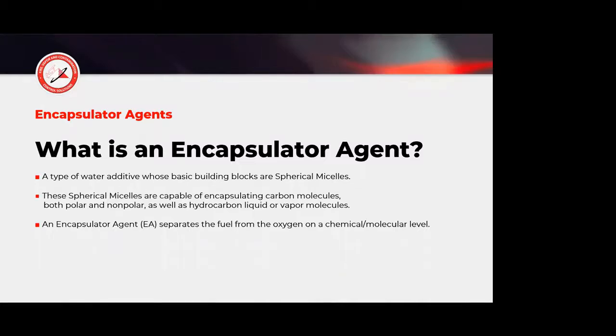So these micelles are capable of encapsulating both carbon molecules and class B materials, both polar and non-polar, as well as hydrocarbon liquids and vapors. So we can encapsulate whether the fuel is in a liquid state or if it's in a vapor state. And that really is going to present a lot of new advancements in fire technology and fire prevention. So basically an encapsulator agent is separating the fuel from the oxygen. We're just doing it on the chemical molecular level as opposed to foam that's doing it on a mechanical macro level. And we'll talk a little bit more about that as we go.